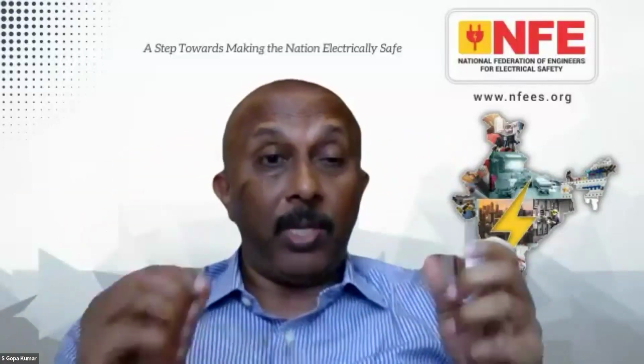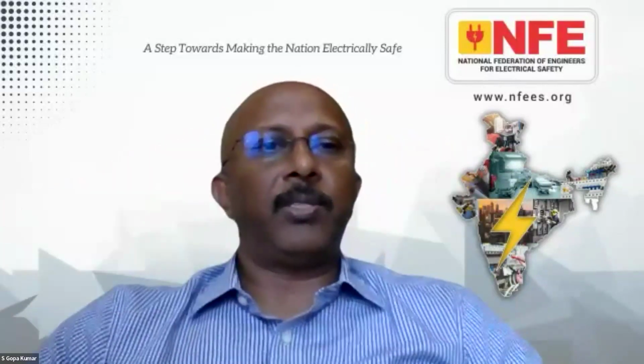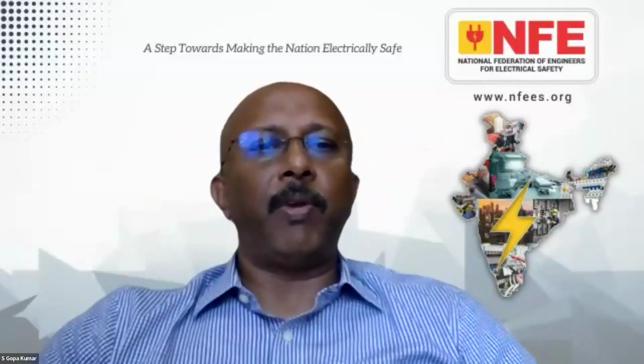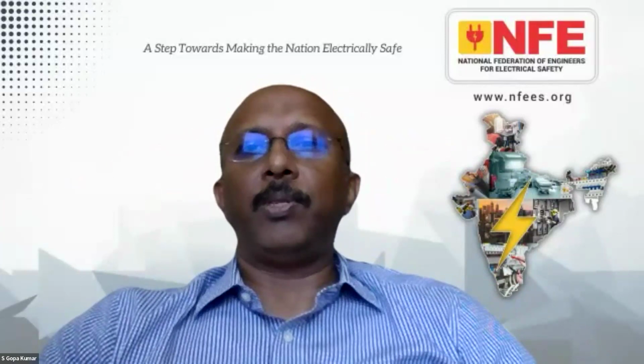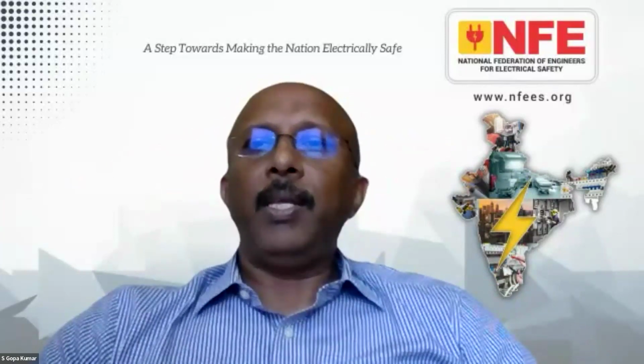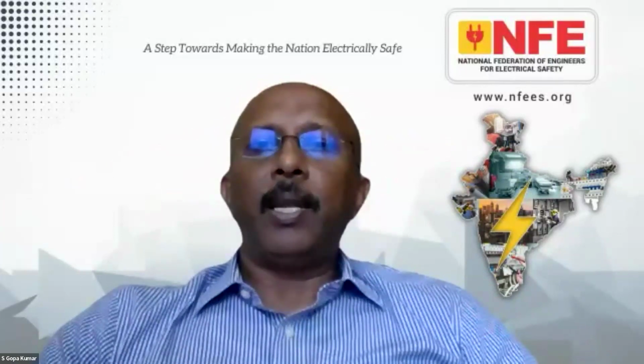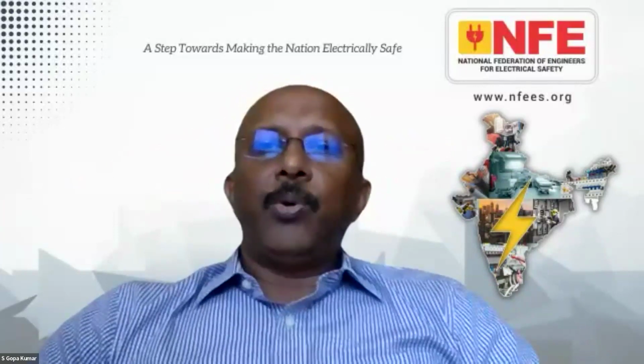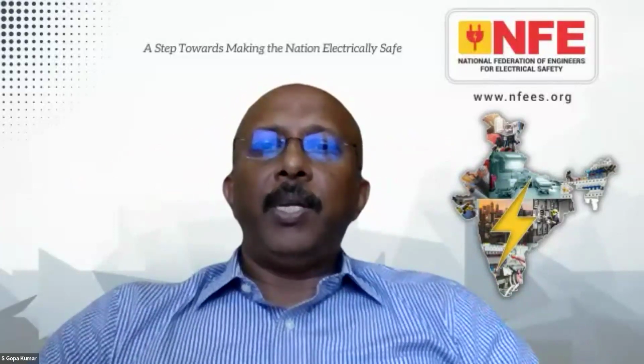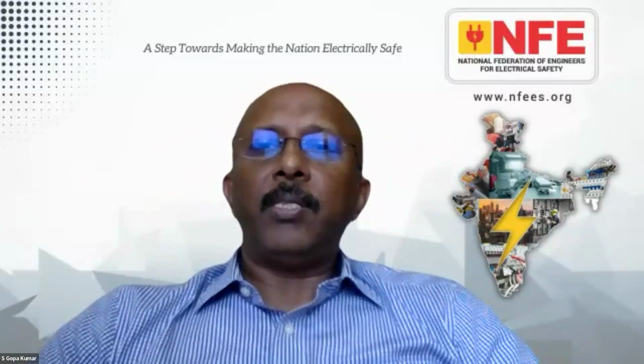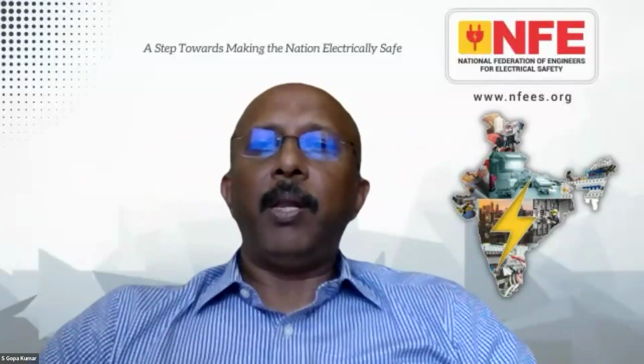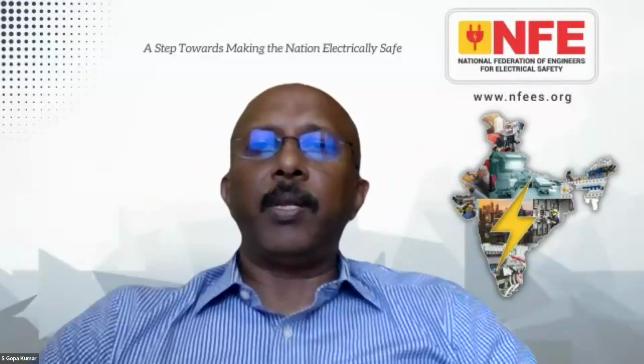But I think the 1000 ampere fault loop impedance tester is probably about 15 to 20 lakh rupees. It's quite expensive. Of course, Mr. Ullas Vajra, it is a live condition, live test. So then Mr. Amit Vyas, multimeter also measures resistance. Then what is the difference between multimeter and the earth loop impedance meter?